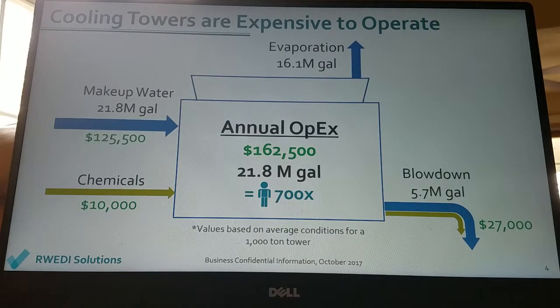So let's take a closer look at how a single cooling tower operates. Here's a typical large cooling tower like those found at major universities. It uses roughly 22 million gallons of fresh water per year, or the equivalent of 700 people. Roughly 70% of that water evaporates to cool the facility. As the water evaporates, scale-forming ions build up in the system, which requires the addition of chemicals to maintain the cooling tower infrastructure. Once those ions reach a certain level, they must be removed from the system through a mechanism called blowdown. Those ions are sent to the sewer. This results in an operating cost of $160,000 per tower. A single institution can operate between 4 to 10 cooling towers.